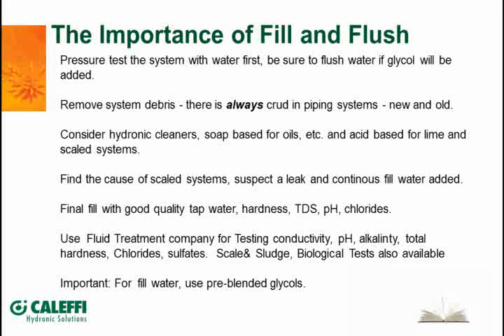So now when you go to clean a system, the cleaner that you choose depends on what you think is in there. Obviously, if it's a new system that might have some oils or greases in it, then you're going to have to use a soap-based cleaner, and there's plenty of companies out there that offer hydronic system cleaners that will clean that out. Now, if you're talking about a retrofit on an existing system where maybe there was some hard water, maybe it had a leak and it had been taking on fill water for years and years, that tends to have a lime scale or calcium buildup, and the soap-type cleaners aren't going to go after that. You're going to need an acid-based cleaner to clean the deposit out of the piping and out of the heat emitters, the radiators, whatever the system might have.